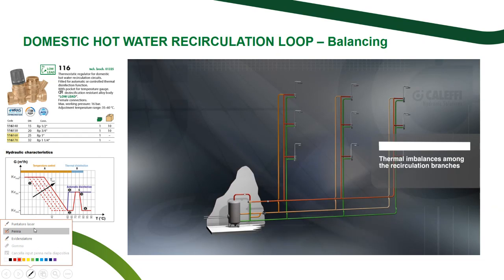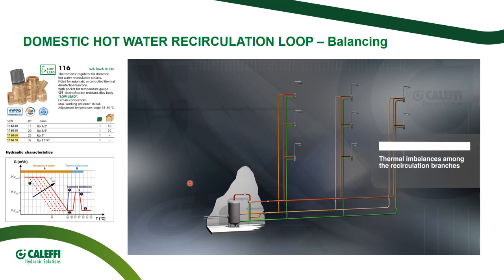So, of course, once we size the recirculation loop for the disinfection, we have to take into account that we have to keep a branch at a certain temperature for a certain period of time. So we have to take into account the hydraulic characteristic of the valve. You will see in the technical data sheet that there are different kV values of the valve. There is kV max, there is kV min, that is the modulating one, the throttling when the valve starts reducing the flow to the minimum, and there is kV disinfection.